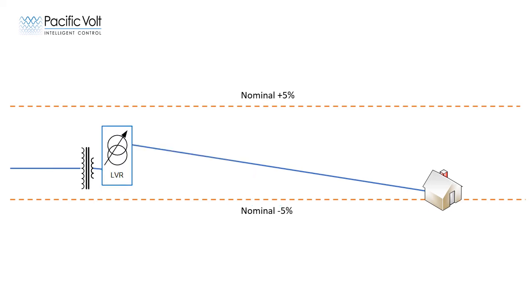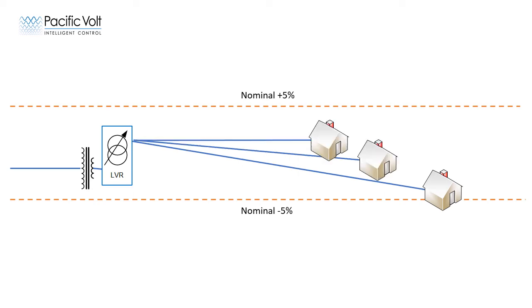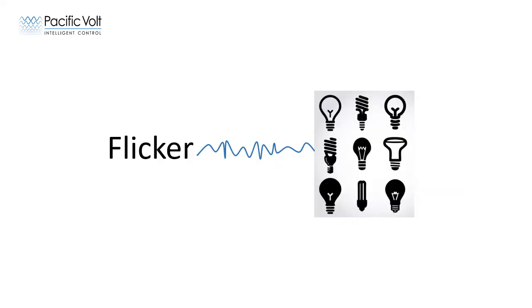For a building that is a long way off the road, an LVR can be installed in lieu of a primary line extension and moving the transformer closer to the building in order to shorten the secondary conductor. Additionally, an LVR can often be installed at the transformer to serve more than one connected house.